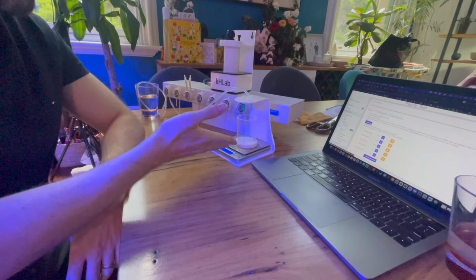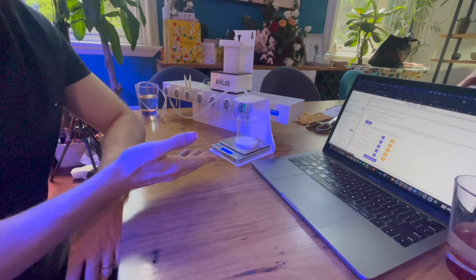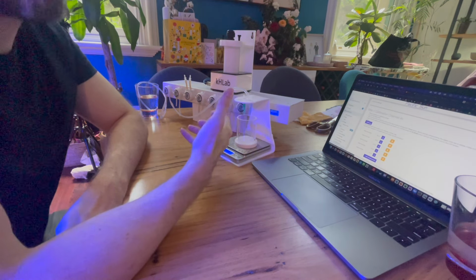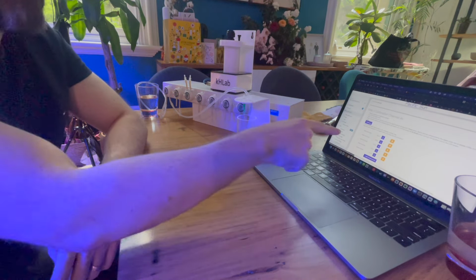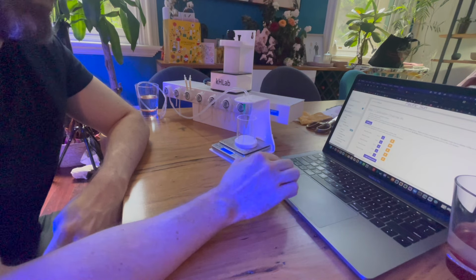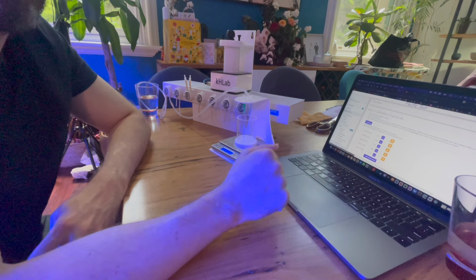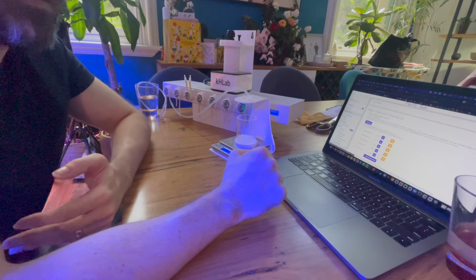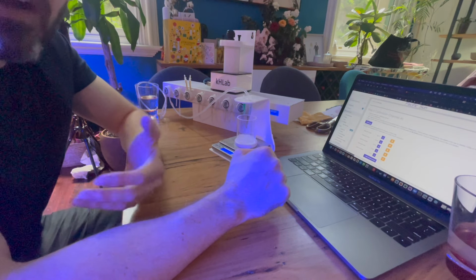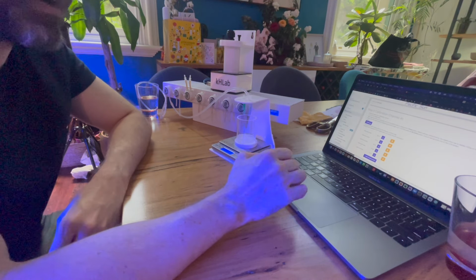And it's going to do the same process, refill the vial. Now you essentially repeat this 5 times, because there's 5 boxes on the interface, and once you've entered values in all 5 boxes, it uses them as an average over the 5 runs to get a really accurate calibration.